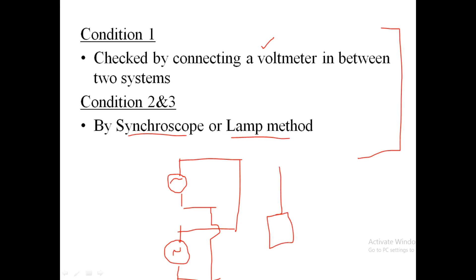So if we are having the same voltage in both the systems, then no current will flow in between the systems. If the voltages are not same, both the alternators are at two different potentials, and a current will flow in between the systems. So that current is known as circulating current. This should not flow because in a parallel operation, both the alternators should supply current to the load. So this circulating current should not be there in case of a parallel operation.